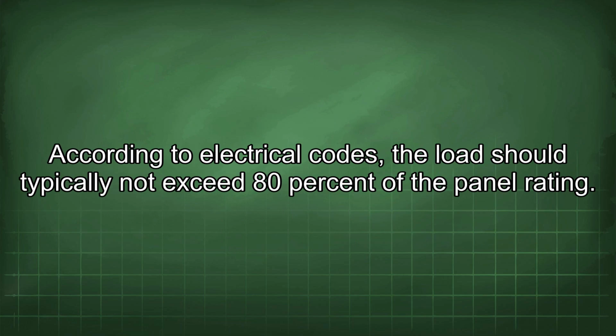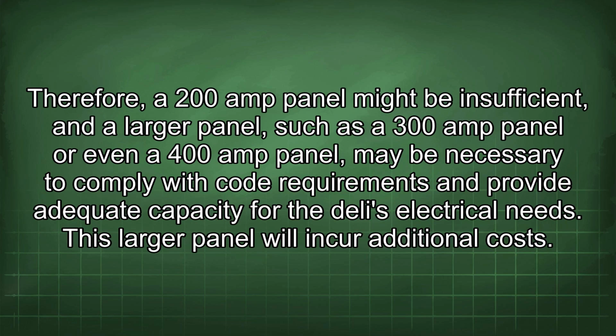According to electrical codes, the load should typically not exceed 80% of the panel rating. Therefore, a 200 amp panel might be insufficient, and a larger panel, such as a 300 amp or even a 400 amp panel, may be necessary to comply with code requirements and provide adequate capacity for the deli's electrical needs. This larger panel will incur additional costs.